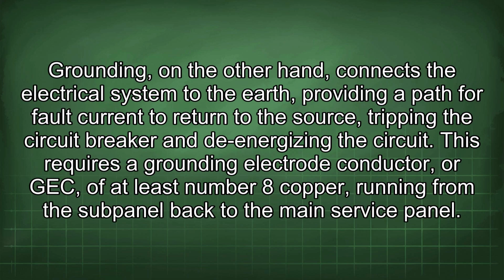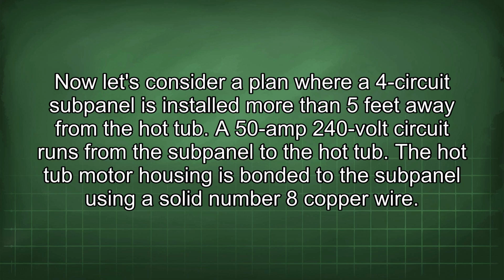Grounding, on the other hand, connects the electrical system to the earth, providing a path for fault current to return to the source, tripping the circuit breaker and de-energizing the circuit. This requires a grounding electrode conductor, or GEC, of at least number 8 copper, running from the subpanel back to the main service panel.